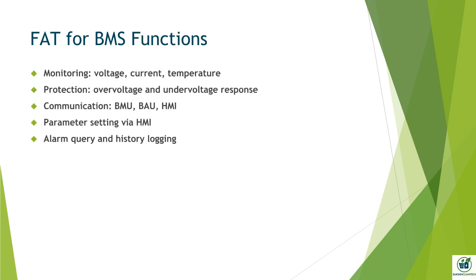Functional testing ensures the BMS can monitor voltage, current, and temperature across all battery strings. Protection functions are triggered when thresholds are breached, such as overvoltage or undervoltage. Communication with BMU, BAU, and HMI must be seamless. Parameters are configured via the HMI, and alarm logs are reviewed to confirm system responsiveness. This ensures the BMS is not just functional, but intelligent.